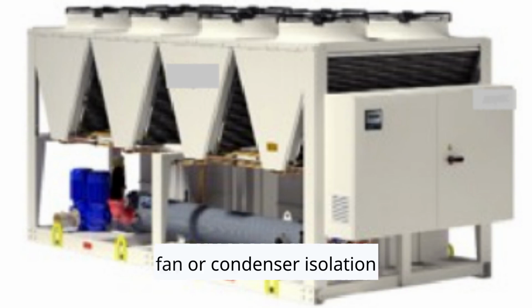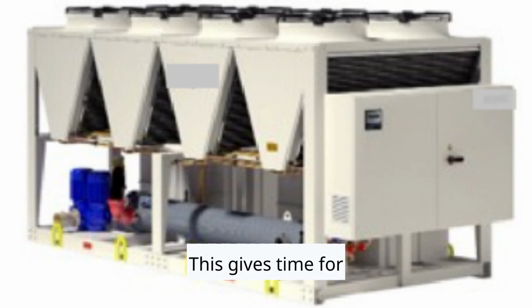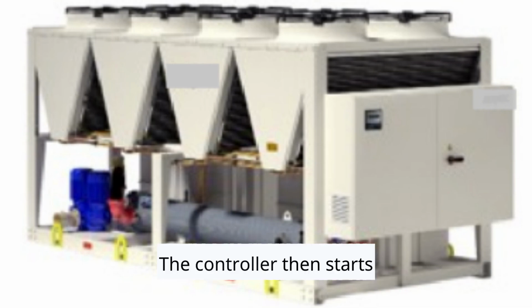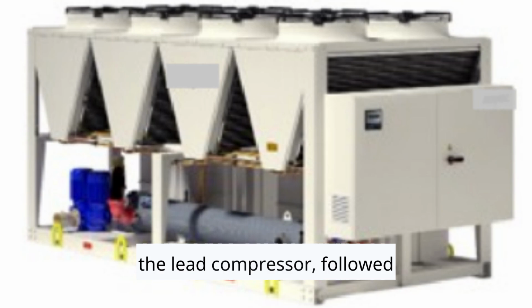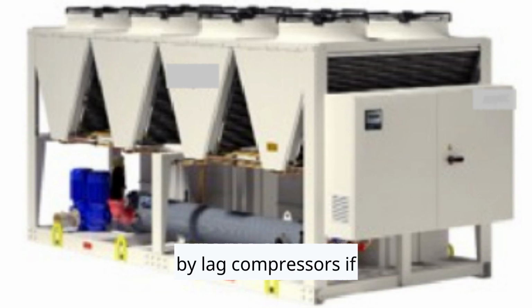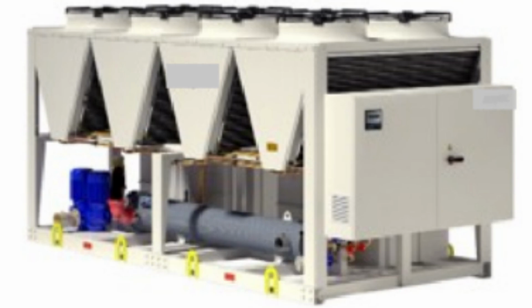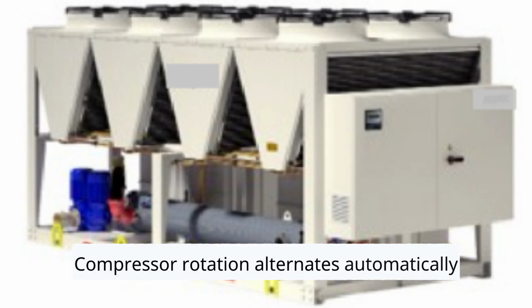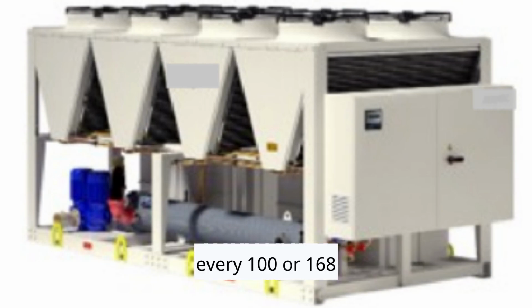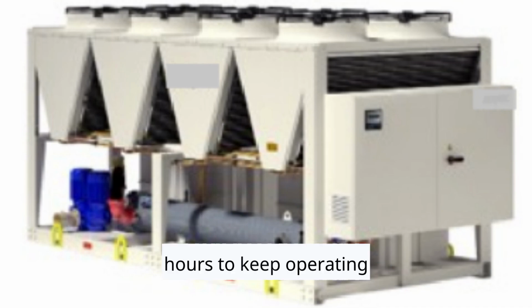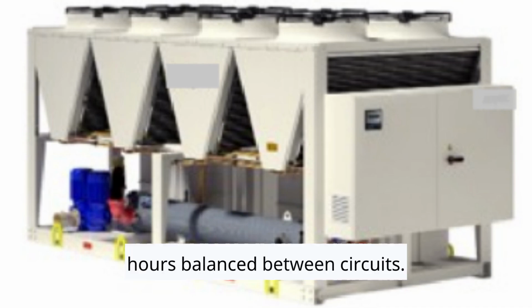The condenser fan or condenser isolation valve turns on roughly 10 seconds before the compressor. This gives time for airflow or water flow to stabilize. The controller then starts the lead compressor, followed by lag compressors if more capacity is needed. Compressor rotation alternates automatically every 100 or 168 hours to keep operating hours balanced between circuits.